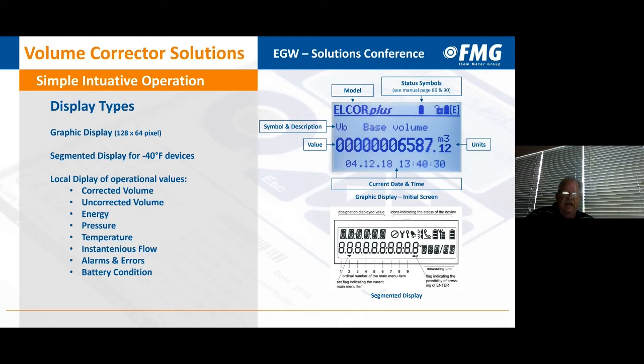And that goes back again to security settings. Where do you want them set? What do you want people to be able to read? Base volumes, corrected, uncorrected, the energy usage, pressures, temperatures, instantaneous flows. This is one of few correctors that will actually give you a flow rate, as well as alarm and error conditions. And if you want to be able to reset those through the front panel, and the condition of the battery. How much longer will that battery last?